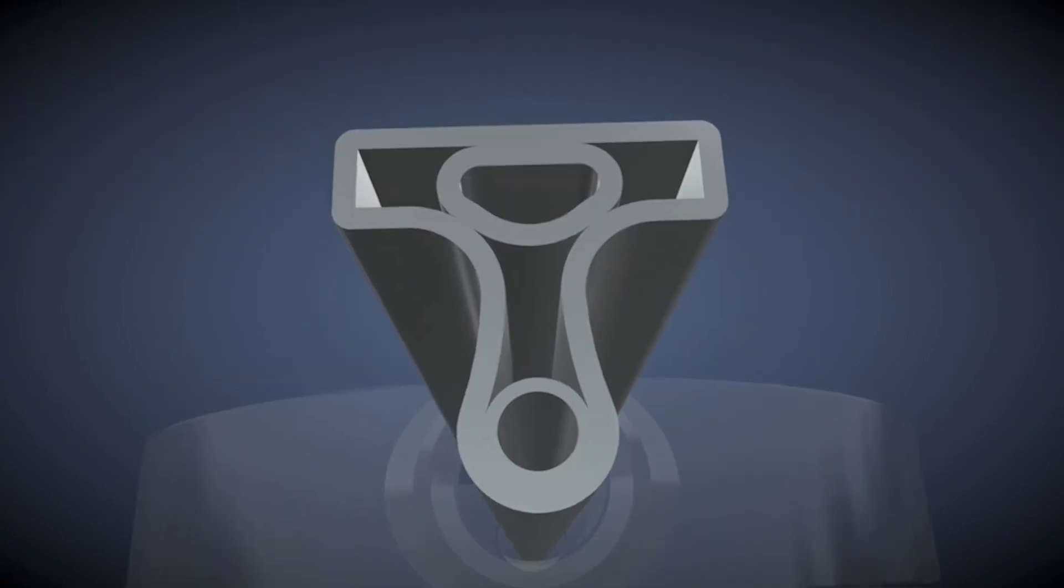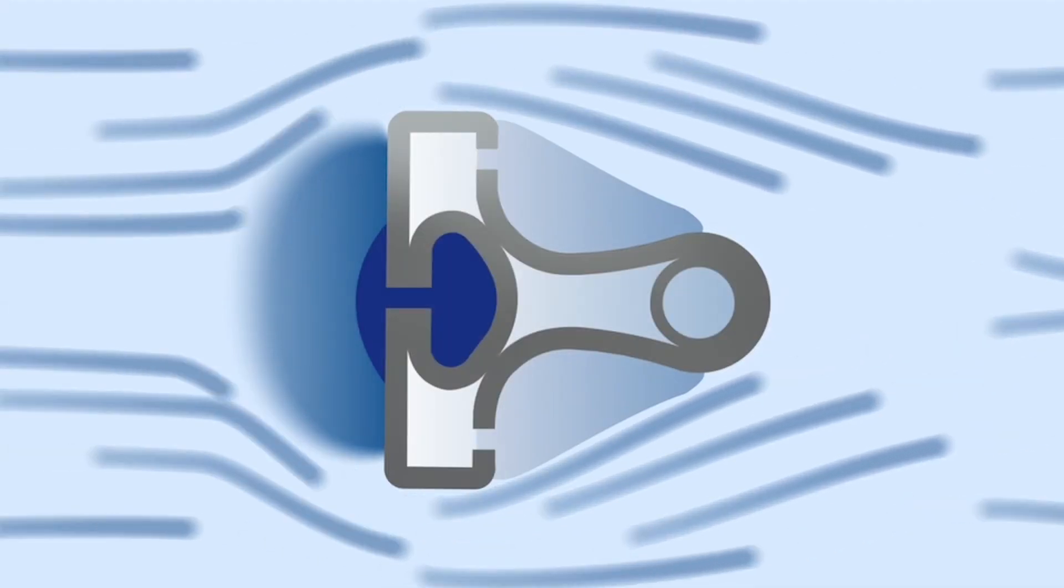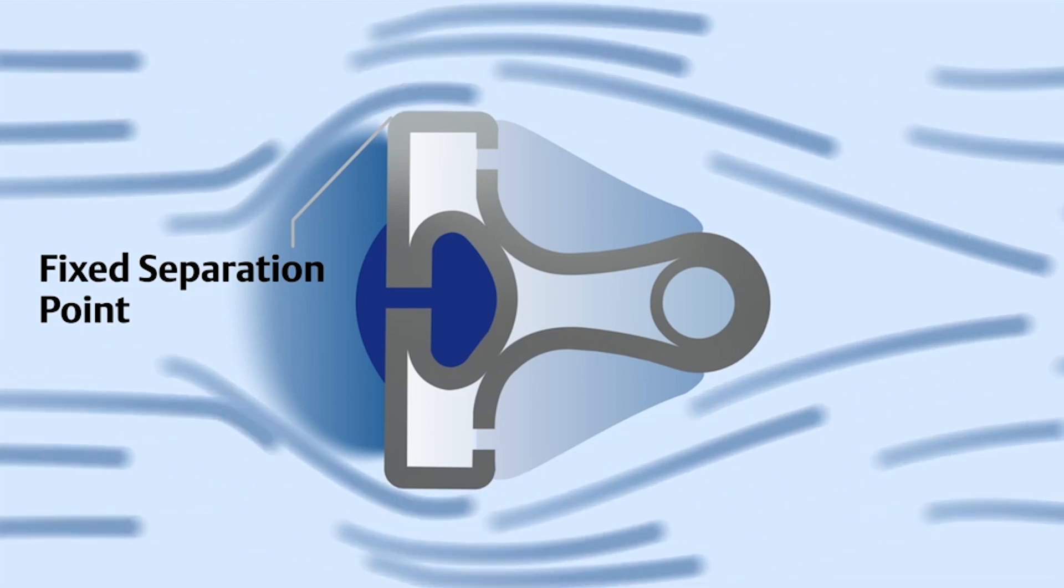Annubar flow meters are equipped with the industry-leading T-shaped sensor. The flat upstream surface of the T-shaped sensor creates a fixed separation point that increases the DP signal and improves performance over a wider flow range.